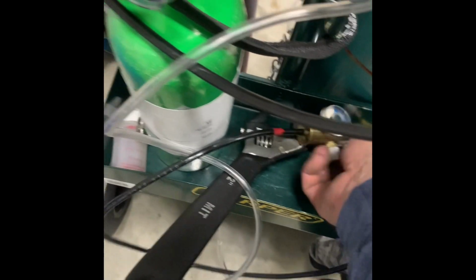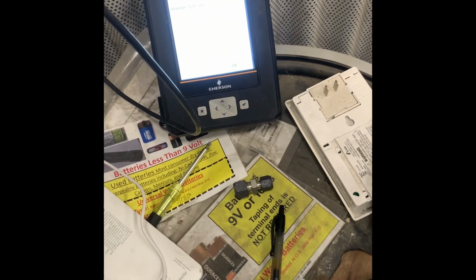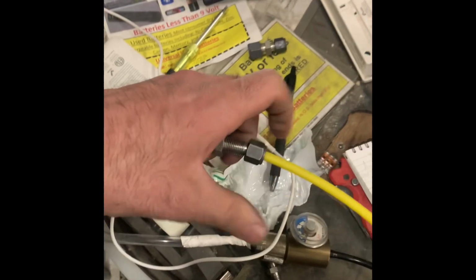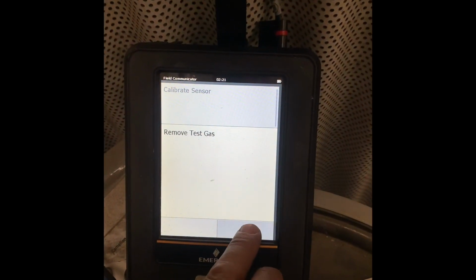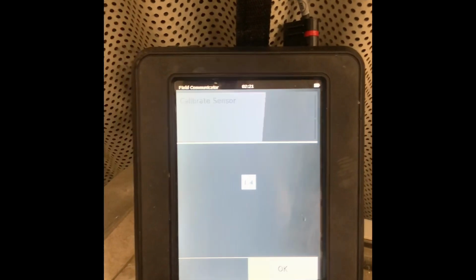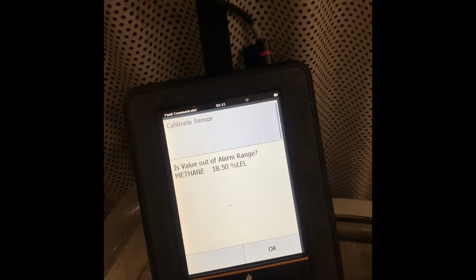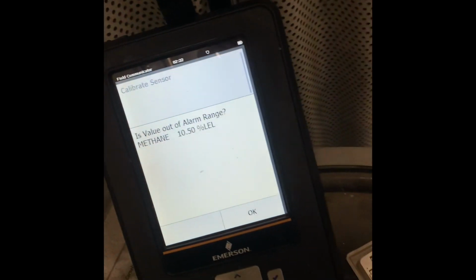And then I'm going to remove the test gas. And normally, if you don't want it to go into alarm, you remove it, run nitrogen through before you get out of the calibration mode, so it goes back to 0. But I want to make sure the alarm works. So I'm going to remove my test gas, hook up nitrogen. I know the line's full of methane, so I'm going to just purge all that through. Right here, you don't want to go back out of cal mode until that's 0, unless you want to test your alarm, which I'm going to do right now.